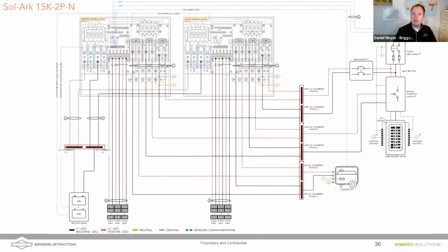Then, in order to operate parallel connections, the output of grid needs to be combined. This would be one load center here, L1, L2. So we have to have a load center to combine up grid, and we have to feed that grid into both of the Sol-Arks. Coming out of the Sol-Arks, out of the load port, we then have to go into another load center and combine their L1s and L2s before we can finally flow out to our main service panels. This bypass switch really is a great idea, because if the inverter system ever fails, we can simply bypass the system, taking grid and making it flow directly into the load service panel.